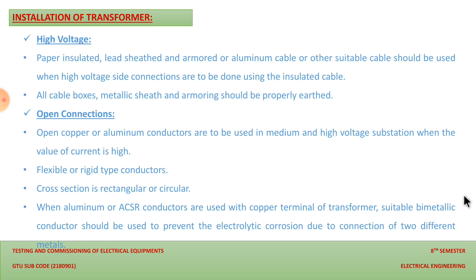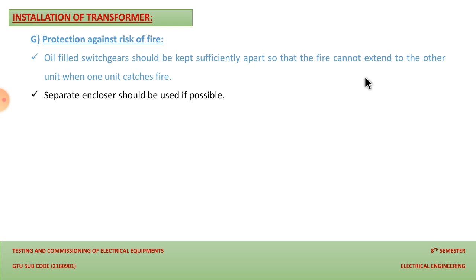Now the next important point is protection against the risk of fire. Oil filled switchgear should be kept sufficiently apart so that the fire cannot be extended, because in switchgear, due to the quenching, an arc will be generated. So it is kept apart for the protection of the transformer. When a unit catches fire because of the operation of the switchgear, it should be kept sufficiently apart from the transformer, and a separate enclosure should be used if possible. Due to separate enclosures, we can avoid flashover between the live parts.